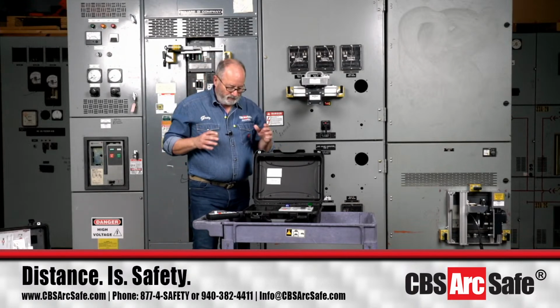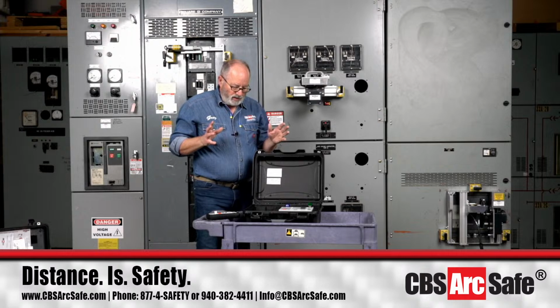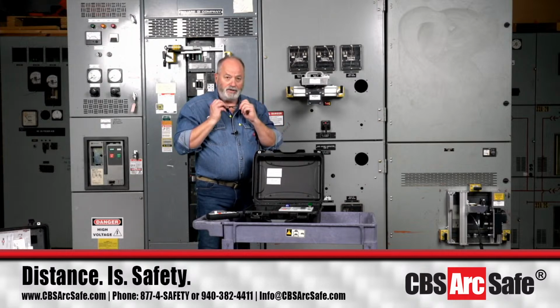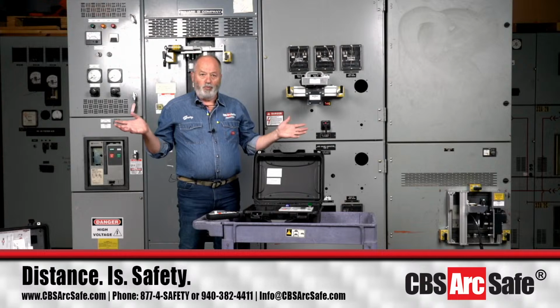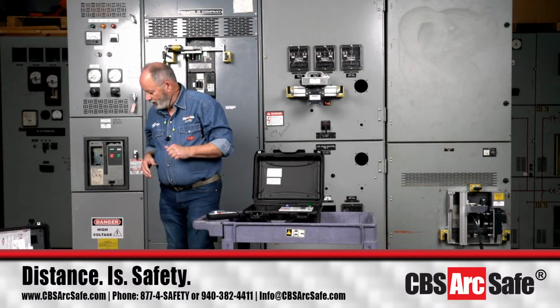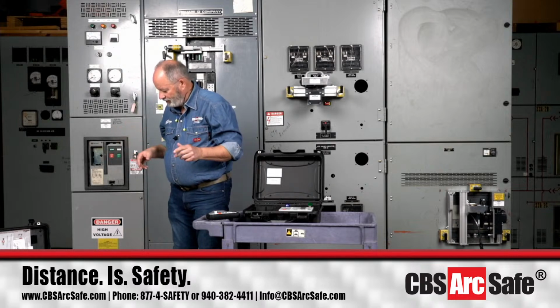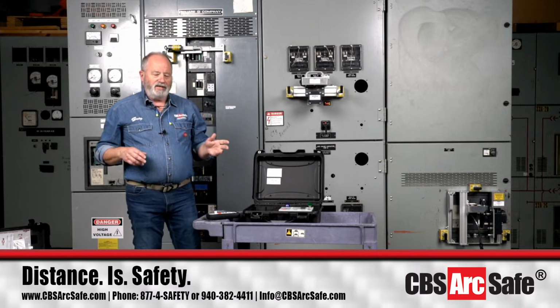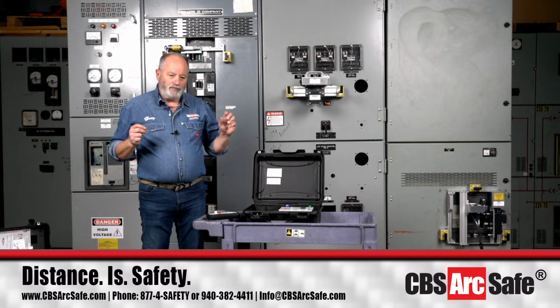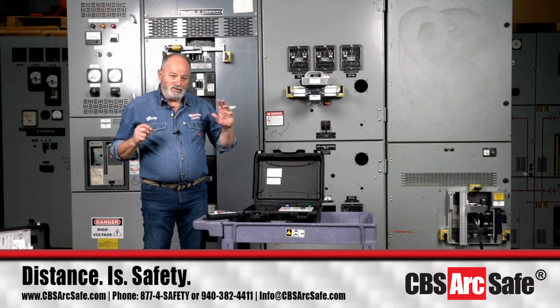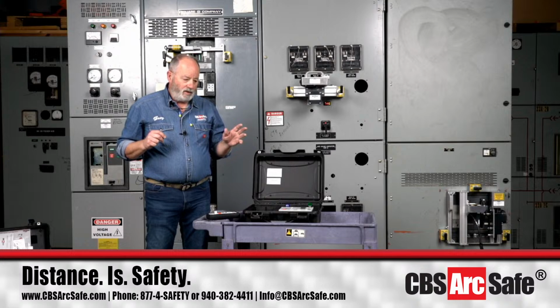The medium voltage breakers are usually, again, one at each end, a knife blade switch, and then your tie breakers for the main-tie-main setup. Understand that when you're doing this, you want to keep people outside of the arc flash hazard boundary.